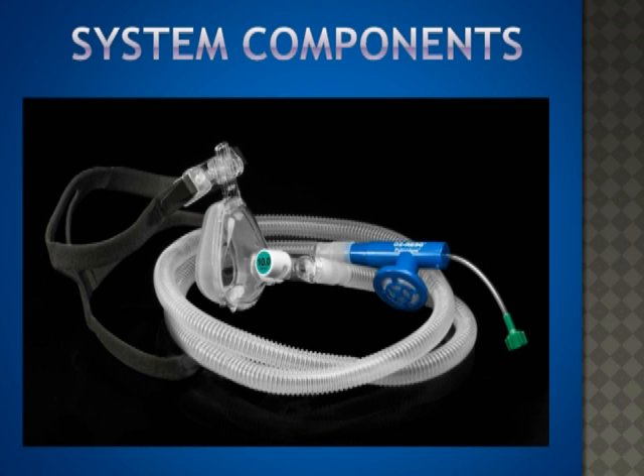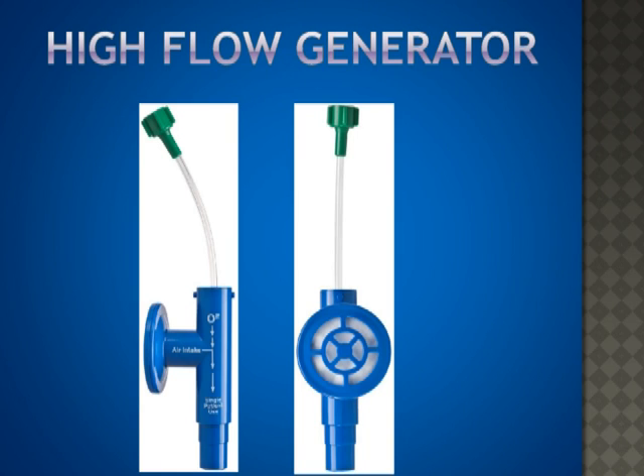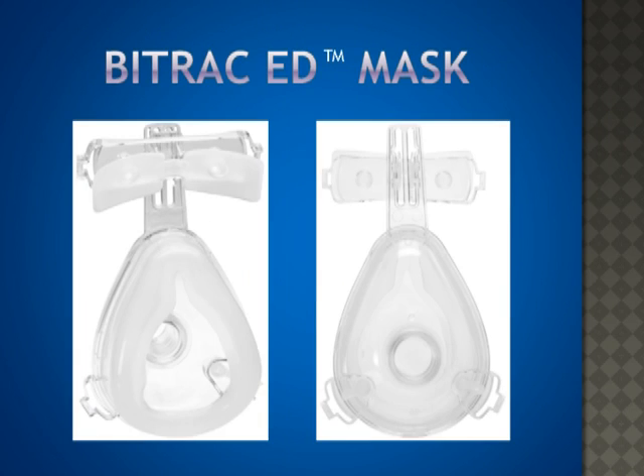Now, let's take a look at the O2 Rescue system and its components. The O2 Rescue generator with a DISS fitting hooks directly to a 50 psi oxygen source. In our case, it'll either be directly to the D cylinder regulator or to the Christmas tree in the truck. There is also a built-in filter to protect any particulate matter from entering the oxygen source. The BiTrac ED mask comes with a multi-positioning Omni clip and a silicone forehead pad. There are dual lip silicone cushions for excellent and comfortable low pressure seal. There are 4 sizes available: adult extra large, adult large, medium, and small. We'll be utilizing the adult large and adult medium. There's also a head strap which comes with dual positioning tabs and attachment clips.